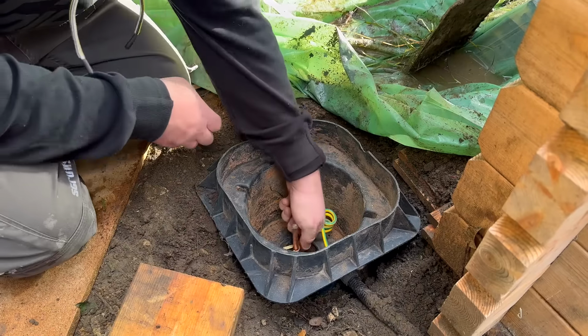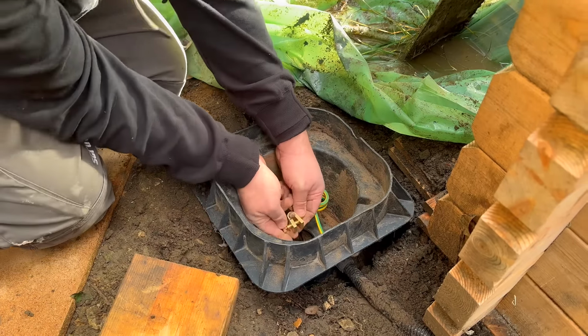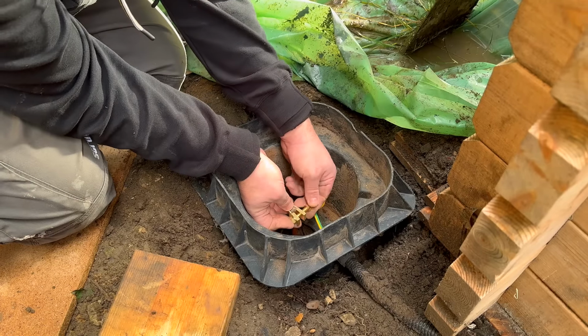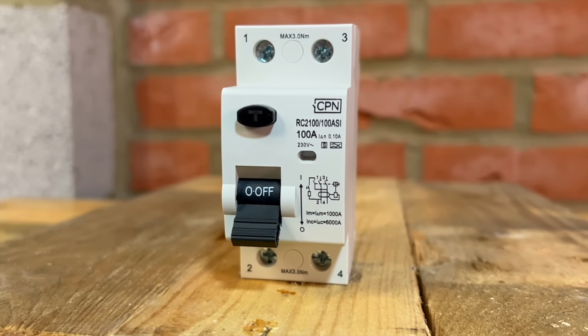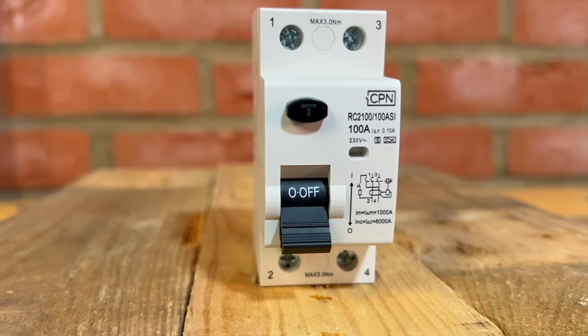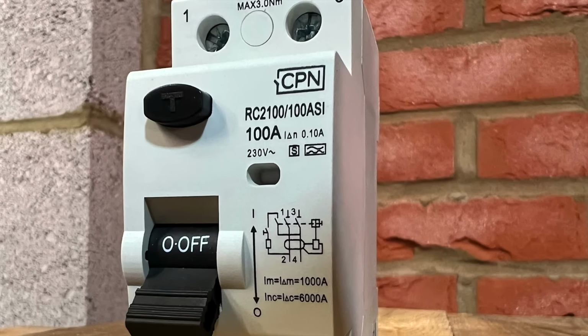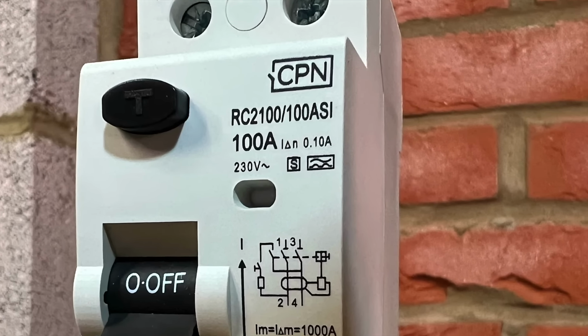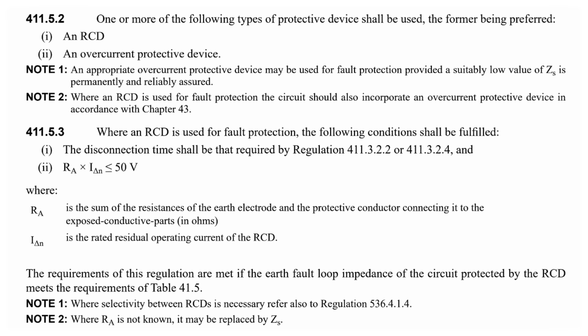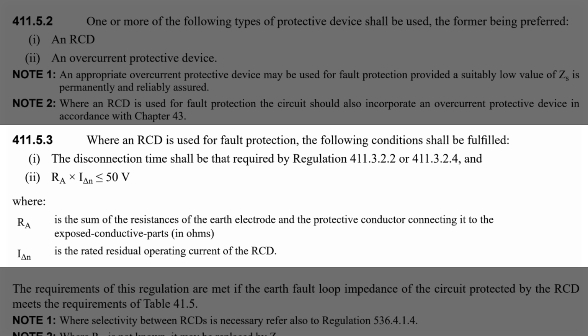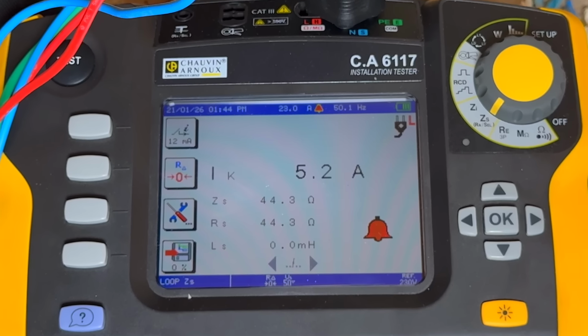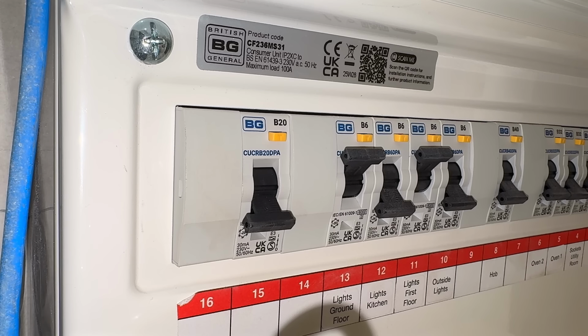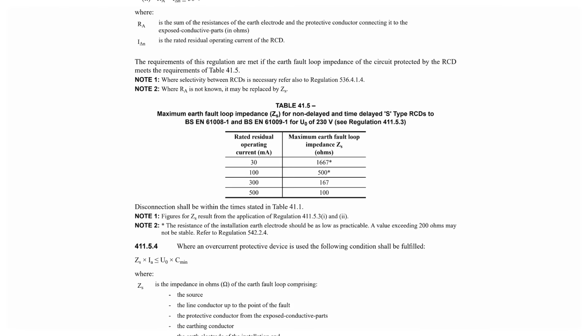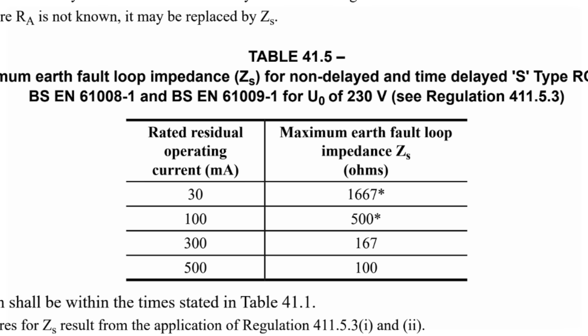On TT systems, BS7671 does not give a single maximum ZE value in the same way it does for TN systems. Instead, the maximum permitted earth fault loop impedance depends on the protective device being used. In most TT installations, fault protection is provided by a time-delayed Type S RCD, and BS7671 sets the requirement that the product of earth resistance and the RCD operating current must not allow the touch voltage to exceed 50 volts. And this is why TT systems can tolerate much higher loop values than a TN system. To put that into context, for a circuit protected by a 30 mA RCD, BS7671 permits an earth fault loop impedance of up to 1,667 ohms.